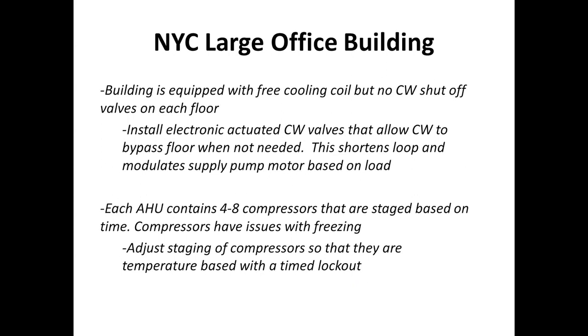What was happening was that 1 minute wasn't enough time. When one compressor kicked on, inevitably a second and a third and a fourth compressor would kick on, and eventually the units would freeze up, the building wouldn't be cooled, and the compressors would freeze up.